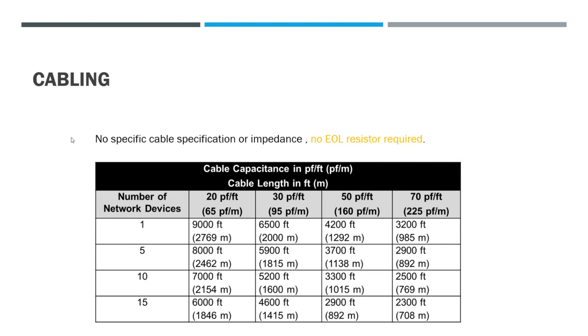That's a good question, because HART really has no specific specifications, while the next protocols we'll discuss do. This relates to increasing technology — the more capabilities you get with digital communication, the more data has to be transferred, so there's more need to ensure the data hasn't been compromised and the signal is adequate. So wire specifications increase as the demand for data increases. HART, being the simplest protocol, doesn't have specific cable specs — no impedance value, no terminating resistor required. I hope that answers your question.